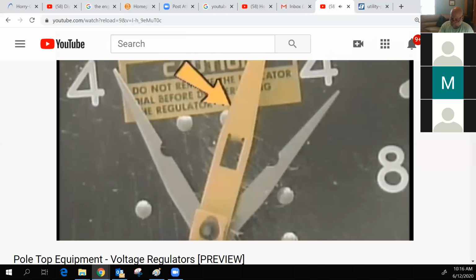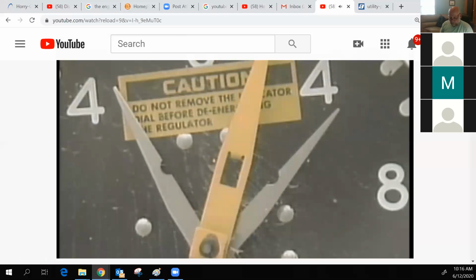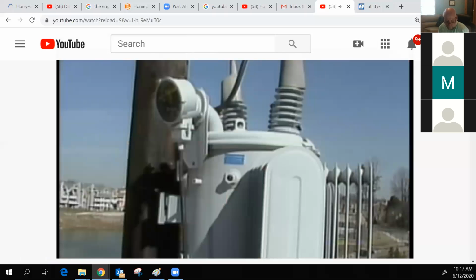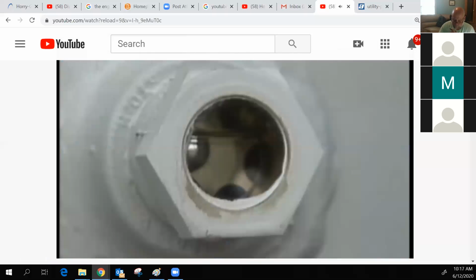The pointer indicates the present tap position of the regulator. In addition, there are two drag hands, which indicate the highest and lowest tap positions that the regulator has moved to since the drag hands were reset. In the tank, oil is used as an arc extinguishing medium. An oil level gauge is located on the tank of the regulator so that the level of the oil can be checked easily.